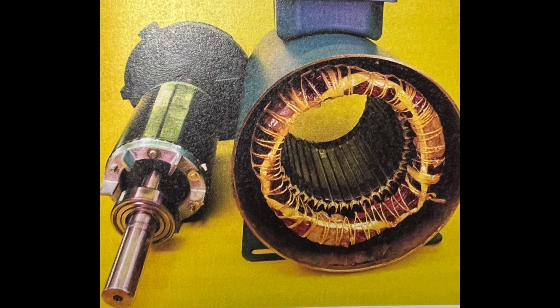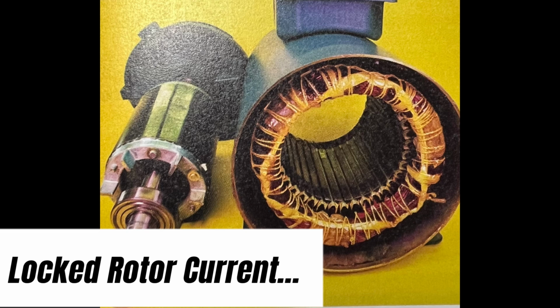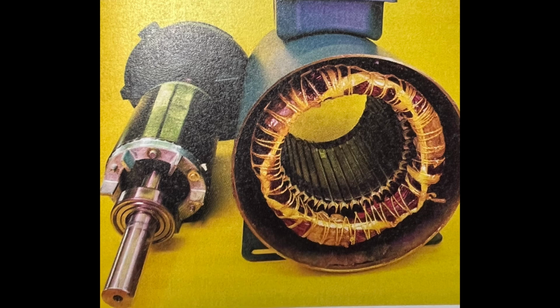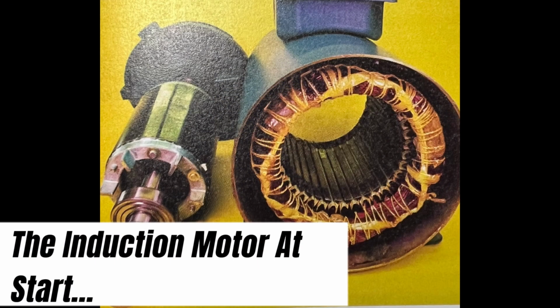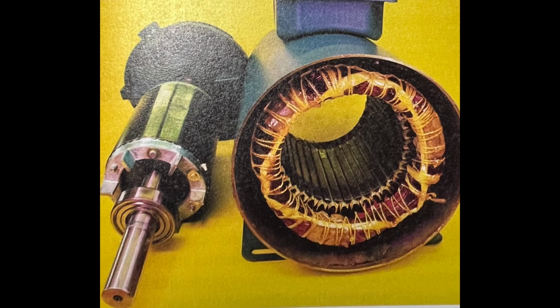Lock rotor currents. The lock rotor current and the resulting torque are factors which determine if the motor can be connected across the line or if the current must be reduced to obtain the required performance. Lock rotor currents for different motor types vary from 2.5 to 10 times the full load current of the motor. Some motors, however, have even higher inrush current. The induction motor at start. Please see the next image for the behavior of the current taken by an induction motor at various speeds.